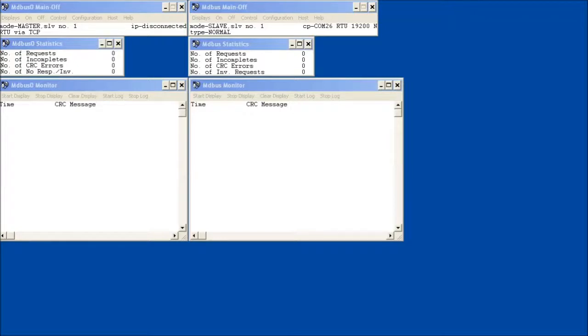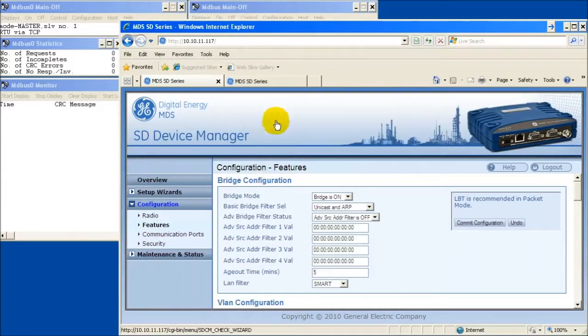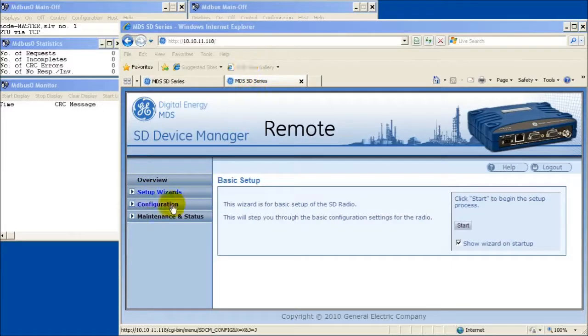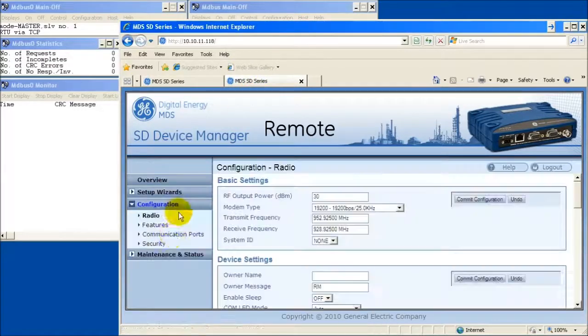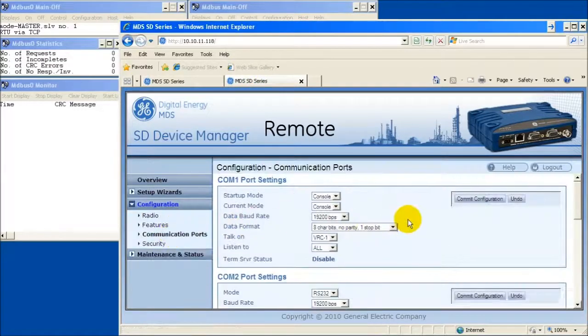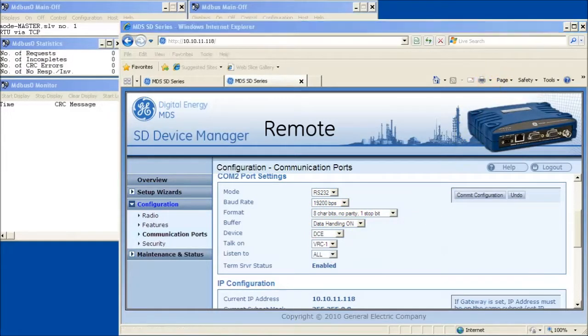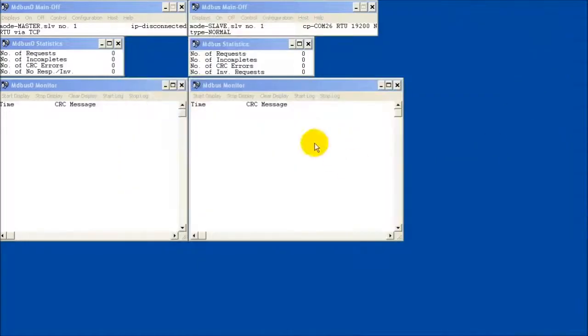To verify these settings, open a web browser to the remote radio and navigate to Configuration then Communications Ports. Scroll down to COM2 port settings. Verify COM2 settings match those of the MDBus slave, which represents the RTU or PLC device connected to COM2 of the SD radio.